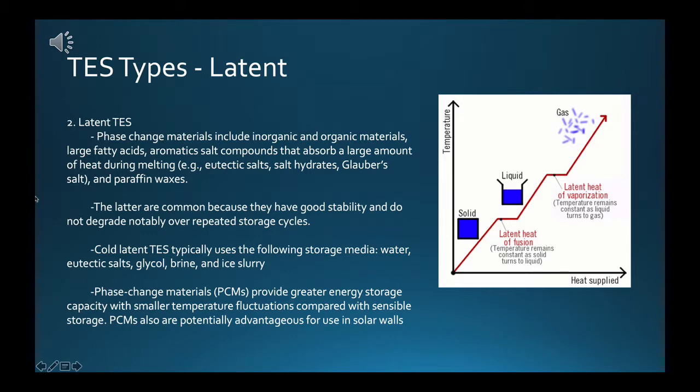Latent heat changes are the heat interactions during the phase change of a material at constant temperature, for example solid to or from liquid. Latent heat TES systems store or release thermal energy as a material changes phase. A latent heat change is usually much higher than a sensible heat change for a given amount of storage medium, giving latent TES a higher energy storage density. Phase change materials include inorganic and organic materials, large fatty acids, aromatic salt compounds such as eutectic salts, salt hydrates, Glauber's salt, and paraffin waxes.